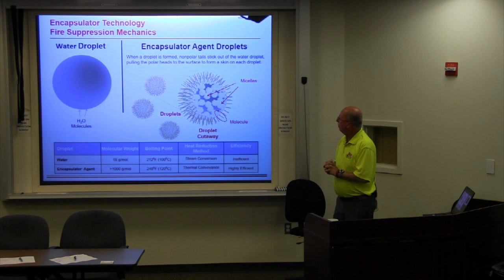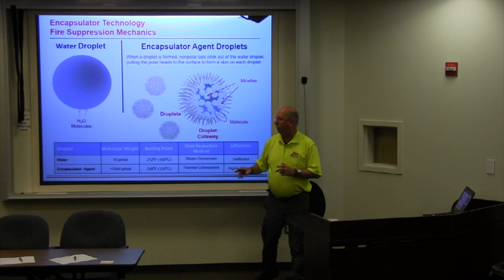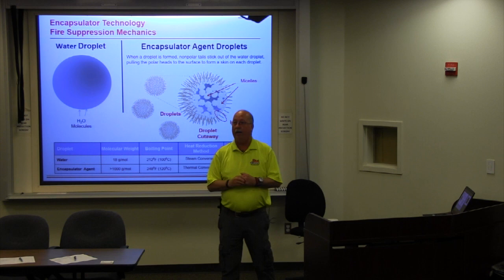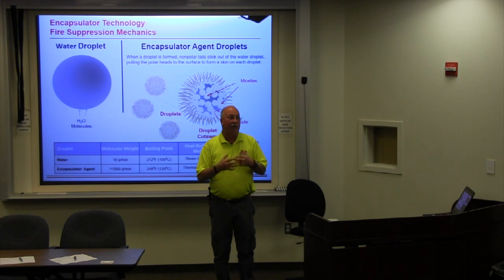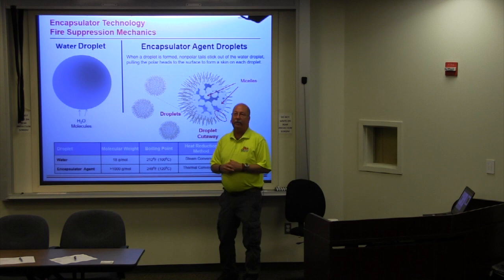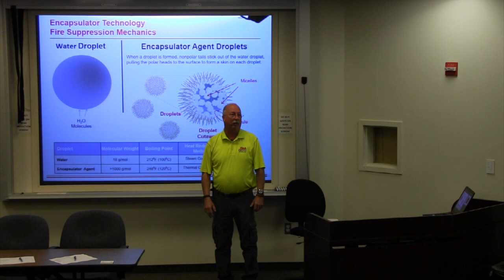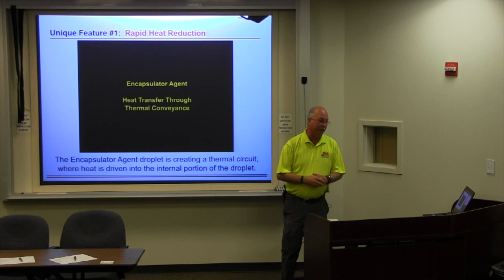Because when you look at a water molecule, at 212 degrees it turns to steam. And steam conversion is what we're really using right now for extinguishing fires. You go into a room, you hit the fire, you get that steam blanket, you hunker down and wait for it to cool off a little bit. Well, now you have the ability to go in and hit that fire with a different type of agent. We have a boiling temperature of 248 degrees. You may think, oh my God, that just means I'm going to get scalded at a higher temperature. No, we do not create steam. There's no steam. We cool by thermal conveyance. And to give you an idea of what thermal conveyance is, you saw all those little tails that stick out of the water molecule.